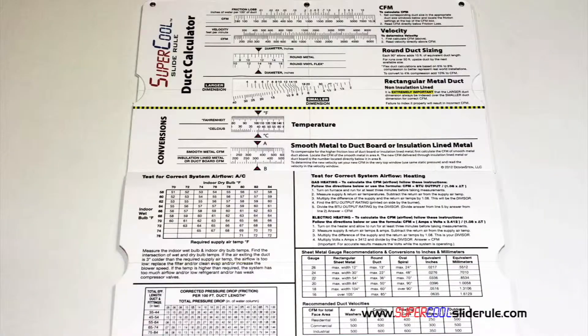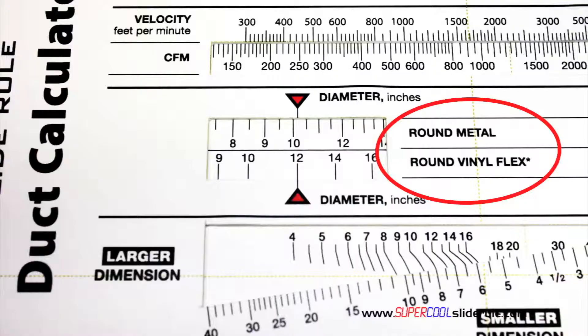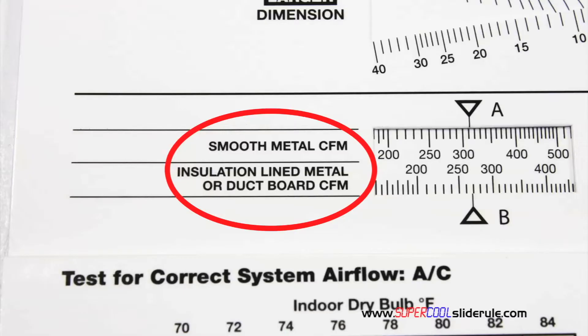Inside is packed with even more information. It performs sizing of both metal and flexible duct, and has the only direct reading conversion from smooth metal to insulation lined metal we've ever seen. The majority of technicians have never been taught that if the insulation is on the inside of the ductwork, you cannot size it with a regular duct calculator.